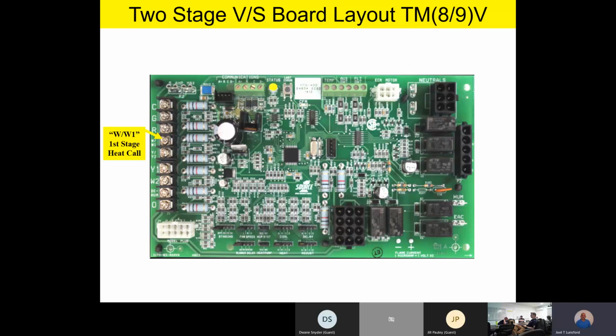Now, it's really important that if for some reason you're stuck with a single stage thermostat, we always want to make sure we land our heating wire on a single stage thermostat on this W/W1 terminal. Because this board, like our previous board we talked about last time, does have some staging capability. Let's say, for instance, you're stuck with a single stage thermostat, you don't have enough wires behind the wall. Maybe the homeowner just really likes that old Honeywell mercury bulb thermostat. This thing would be compatible with that as far as on the heating side. So literally, if I have a single stage thermostat, I can put it on W/W1 and still get some staging capability off of the board, which we'll discuss later on.